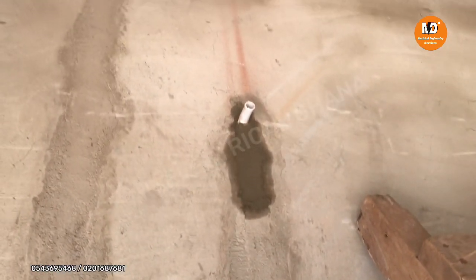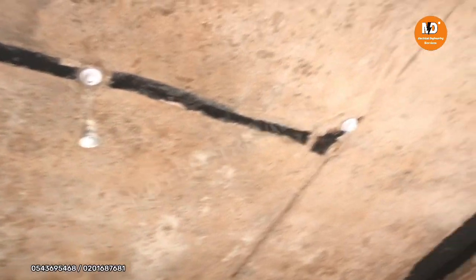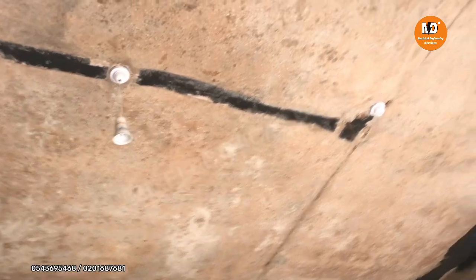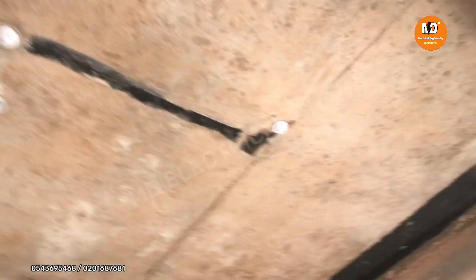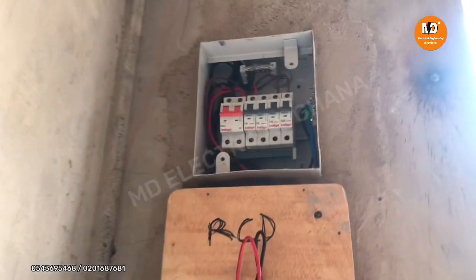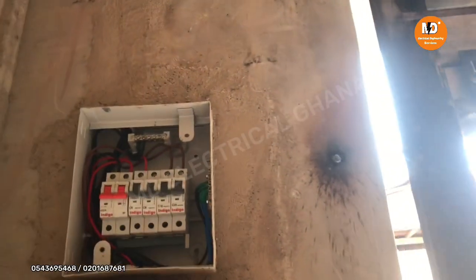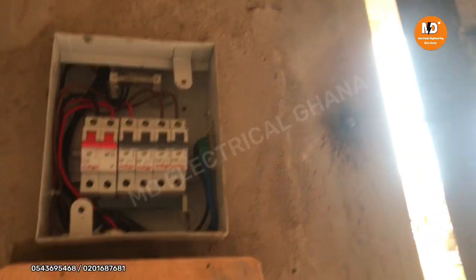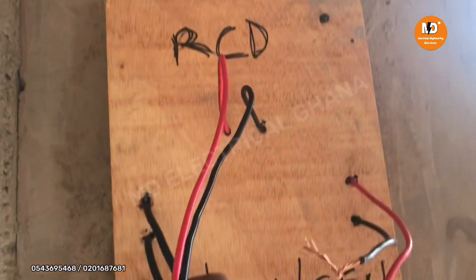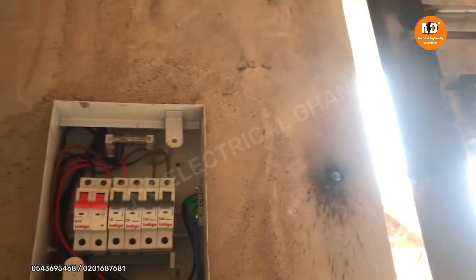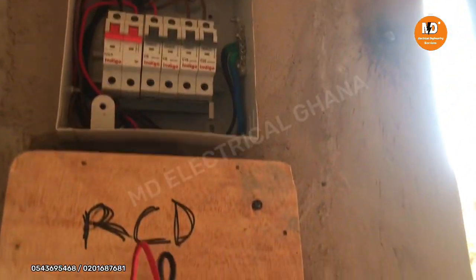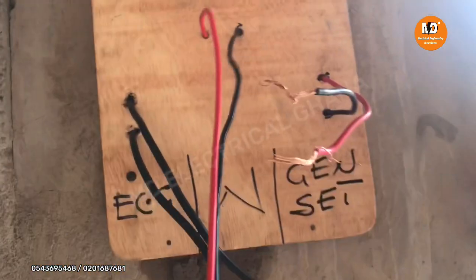The client will go for a POP design. So for now, we are just using these types of holders and ceiling roses to test our system to know that everything is working perfectly fine. Yes, so that's our four-way DB distribution board. You can see it comes with 4 breakers, 4 MCBs, that's miniature circuit breakers. Here we're gonna fix an RCD.